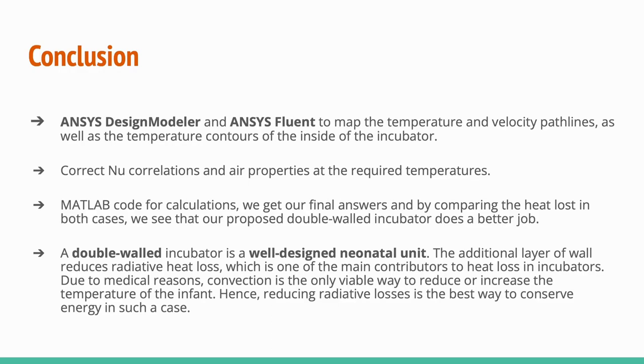For the first part of the model, we used ANSYS Design Modeler and ANSYS Fluent to map the temperature and velocity path lines as well as the temperature contours of the inside of the incubator. Considering that we had assumed the inside of the incubator as a control volume at the same temperature, we got the temperature contours from CFD analysis that matched our hypothesis. For simplification, we also considered the incubator to be approximately rectangular. We then used correct air Nusselt number correlations and air properties at the required temperatures, and using a MATLAB code for the calculations, we got our final answers by comparing the heat loss in both cases. We see that our proposed double-walled incubator does a better job.